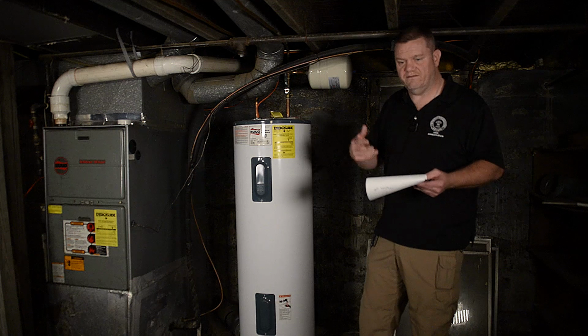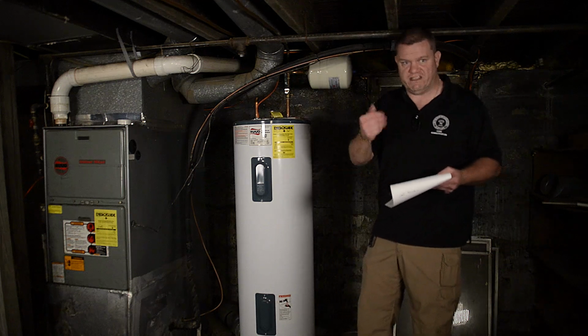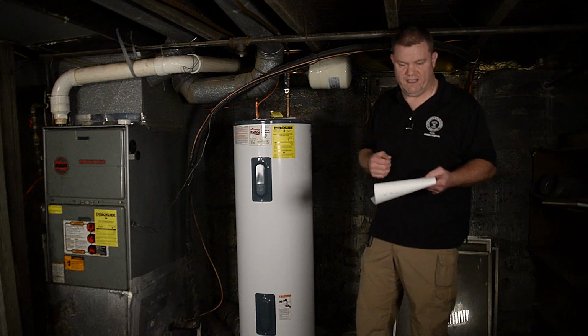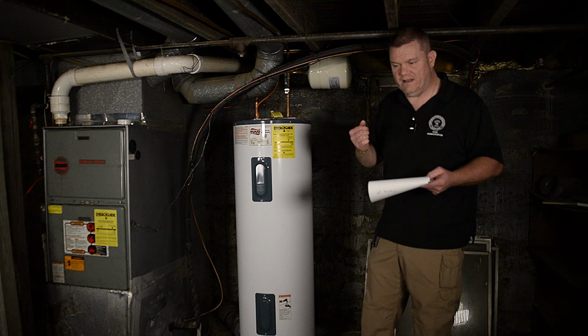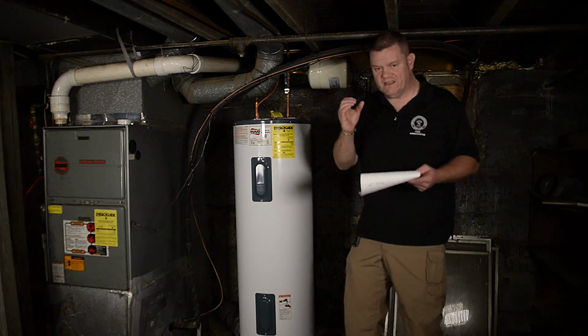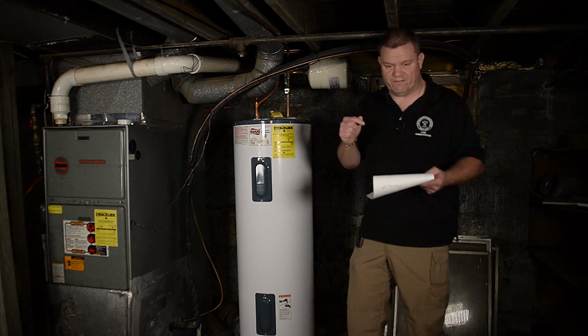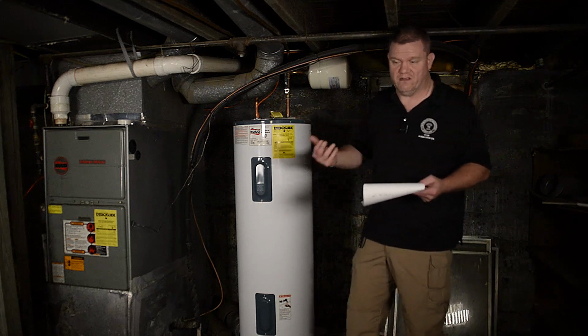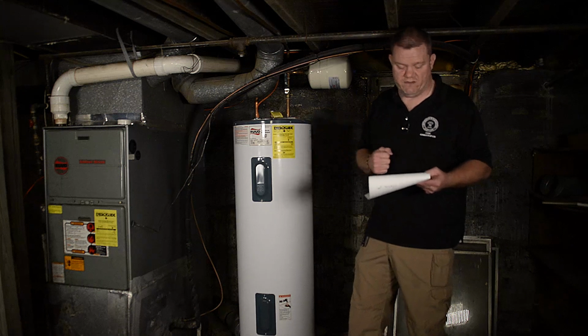With the transition, flex can be used, but not of the vinyl type. And laundry connections themselves, if you're providing the laundry. One little point to touch on, if you do not provide the laundry area and it does have the hookups, we ask that it be capped, because after a while, a trap can dry out and cause a condition of back sewer gases. So please, if we can have those capped.